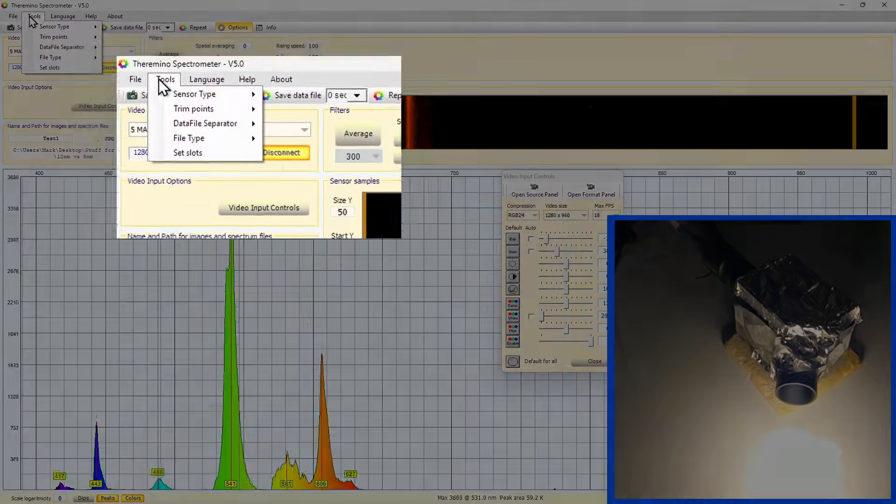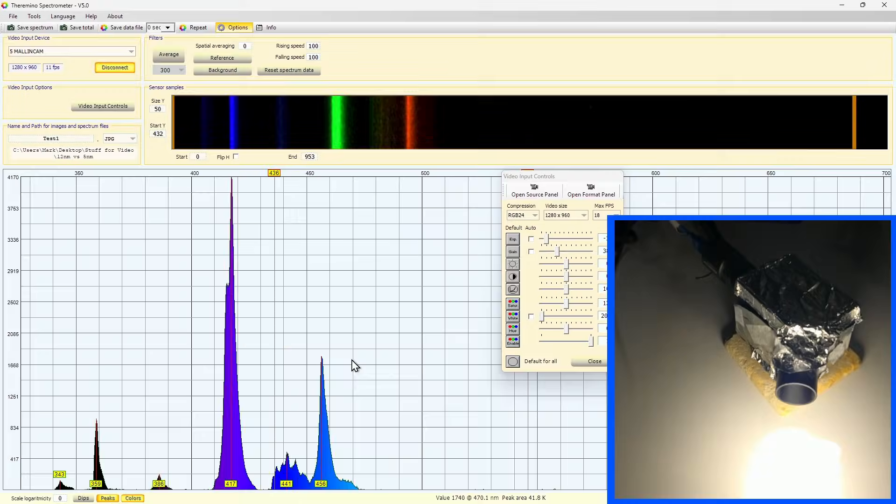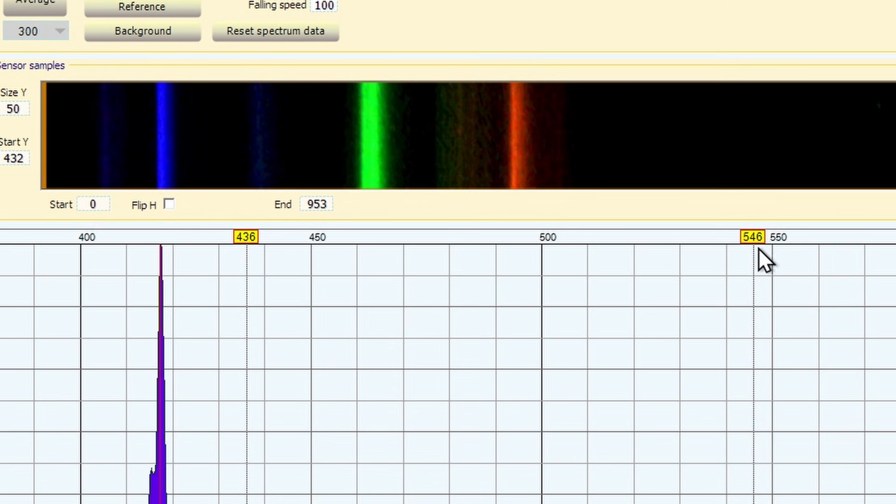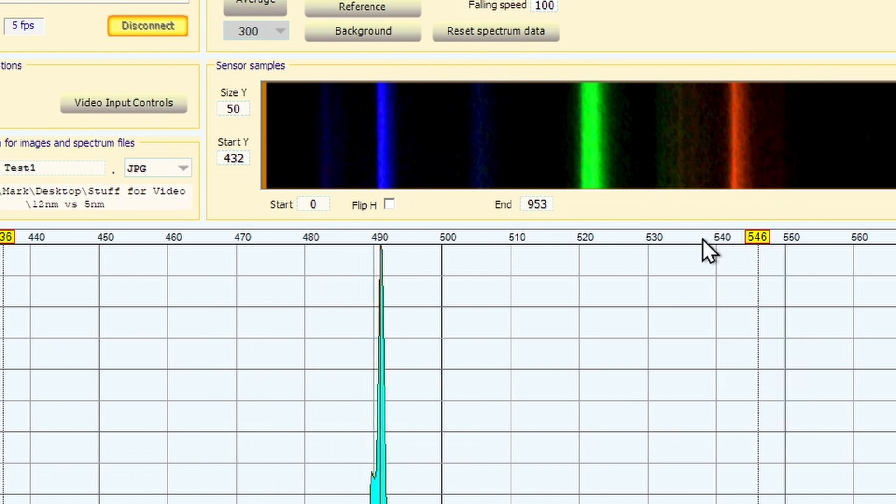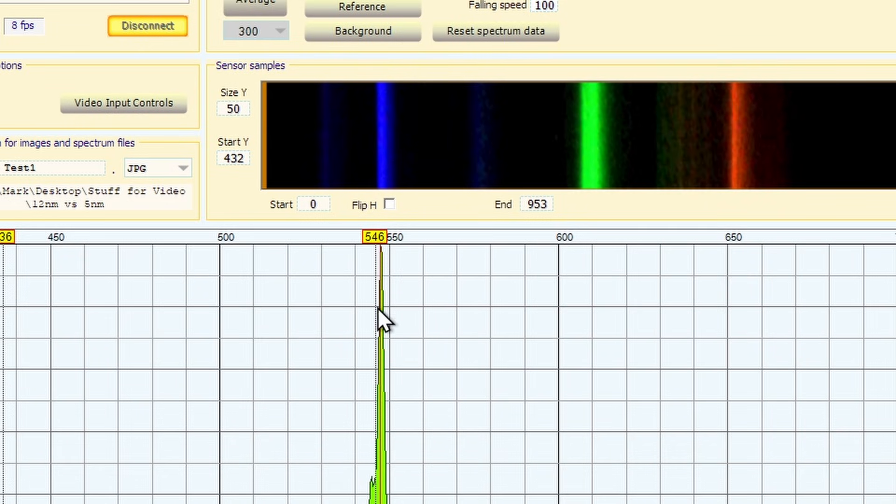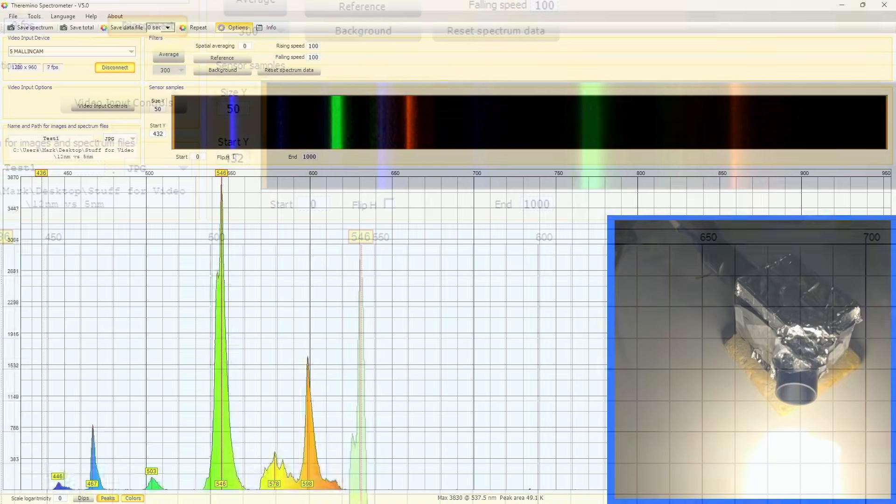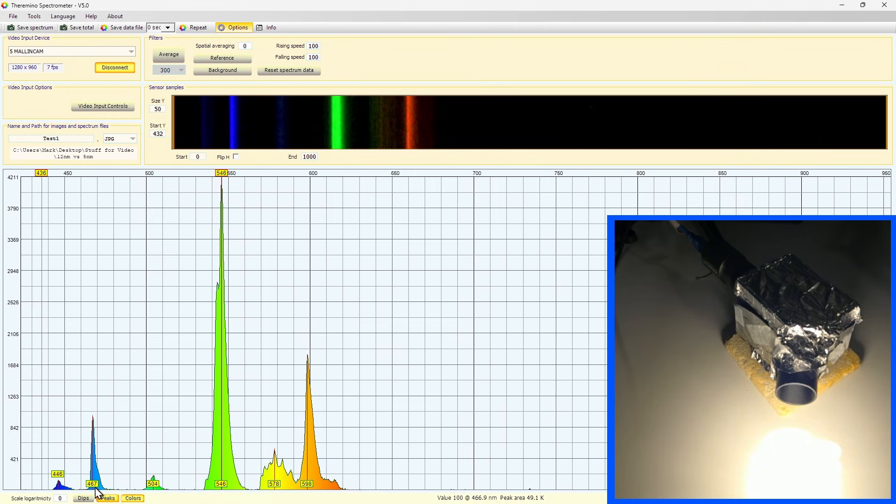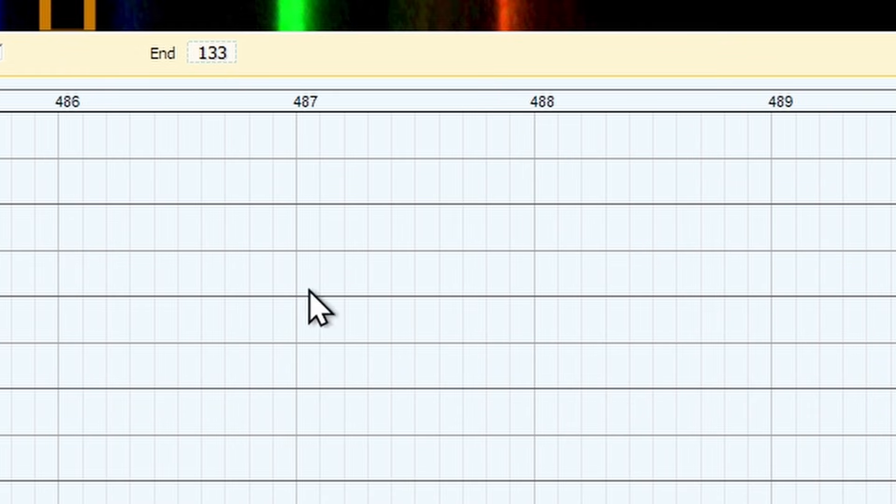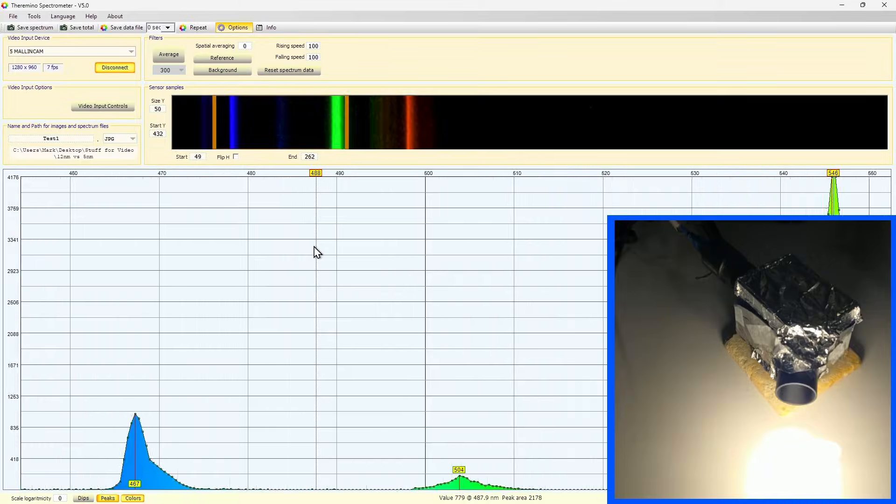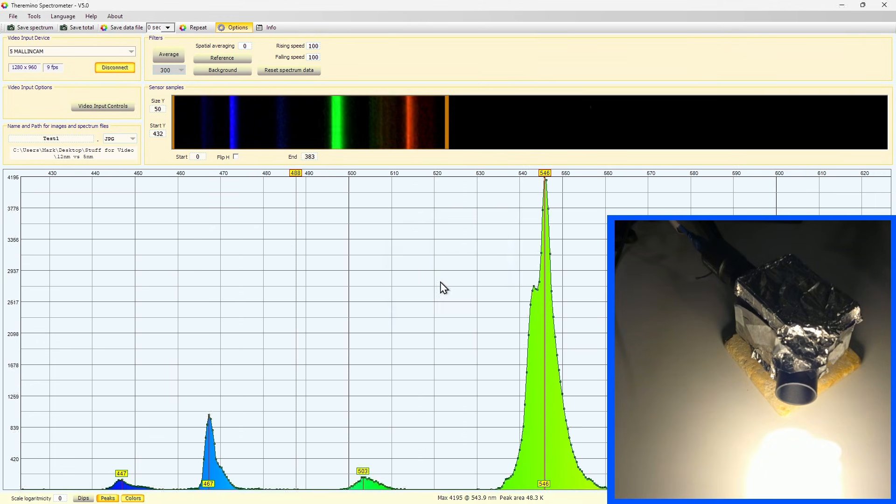So what we need to do is go to tools, trim points and fluorescent 436 and 546. Now the trim points themselves will show up on the X axis up here in yellow. 546 is one that we want to keep. So let's move it over where the Wikipedia page says it should be. Move this one over and then move the 546 over to this very tall peak here. You can use your mouse wheel to zoom in and then just place it right there. Now 436 is a bit too far away from 500 nanometers. So I'm going to use this peak down here, which is around 487 nanometers as my second point. If we right click on the x axis up here, it'll ask you to add a new trimming point. We say yes. And then we can zoom out and right click on the 436, this original trimming point, delete that one.